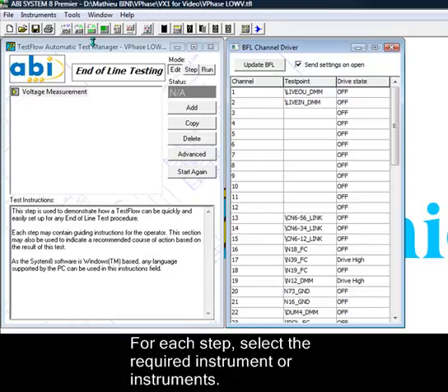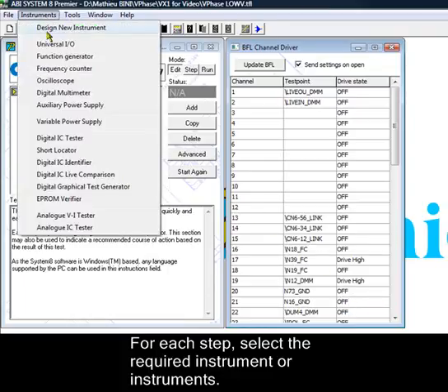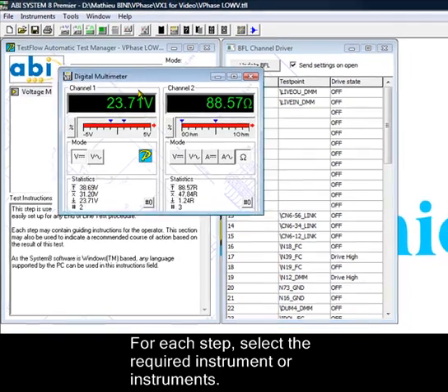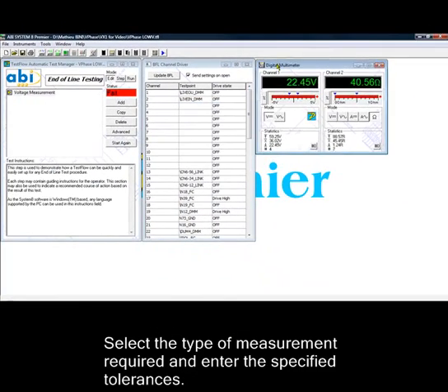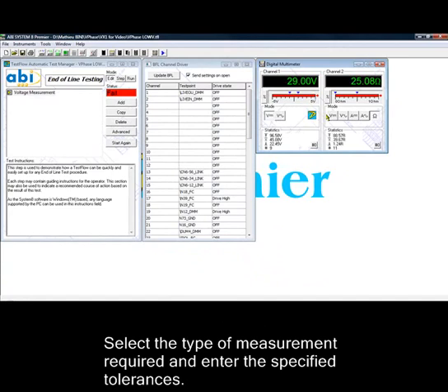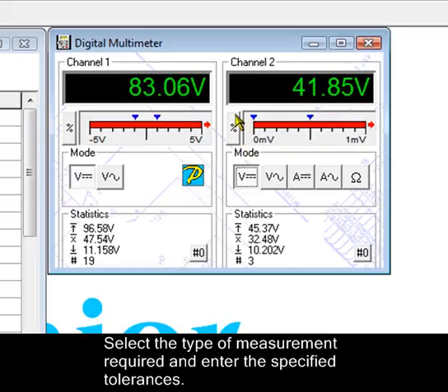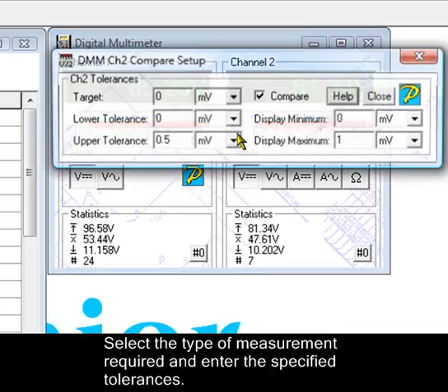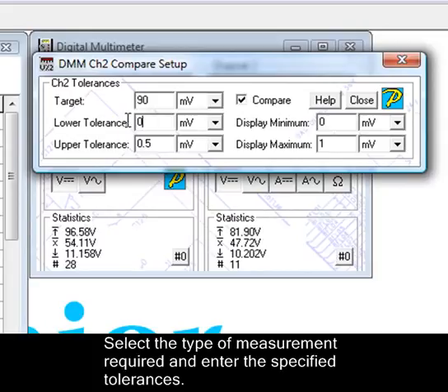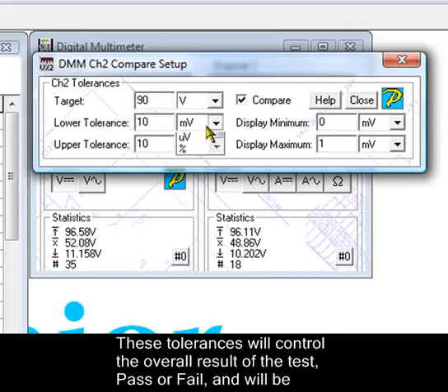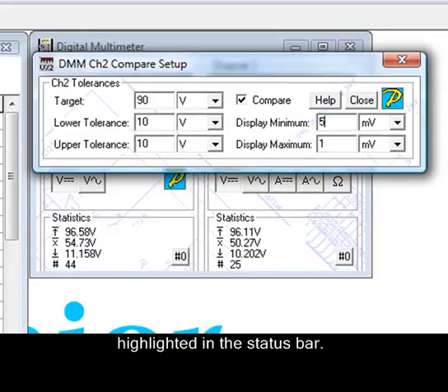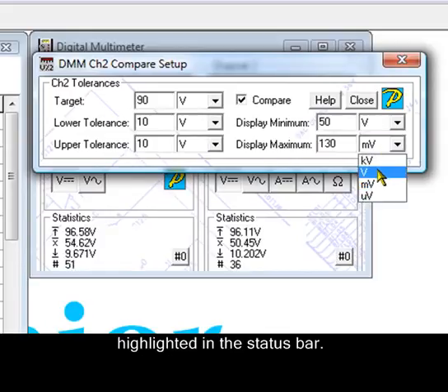For each step, select the required instrument or instruments. Select the type of measurement required and enter the specified tolerances. These tolerances will control the overall result of the test — pass or fail — and will be highlighted in the status bar.